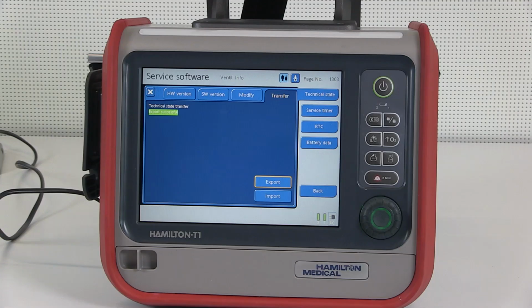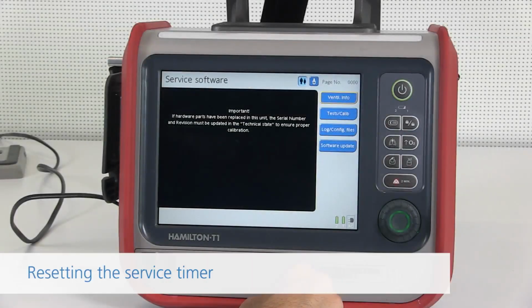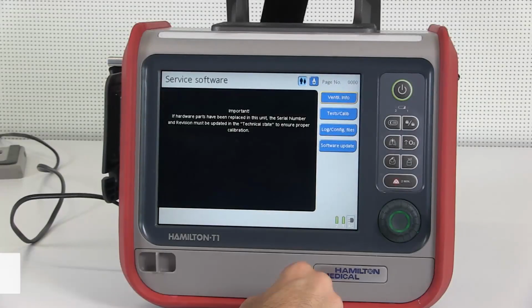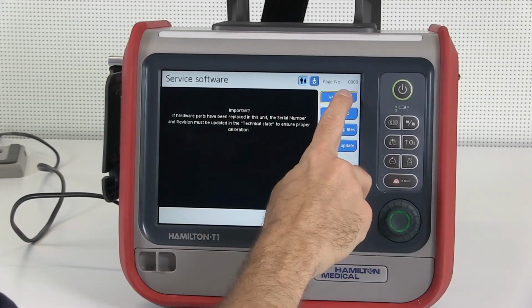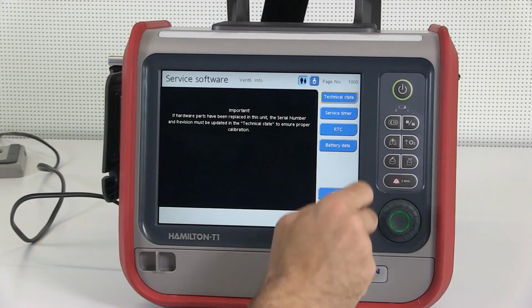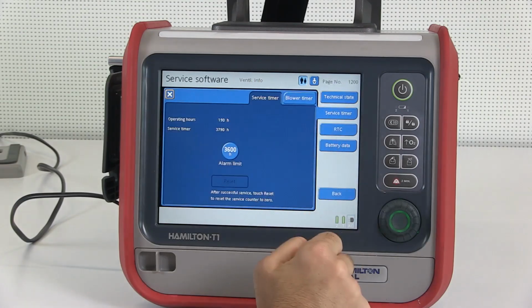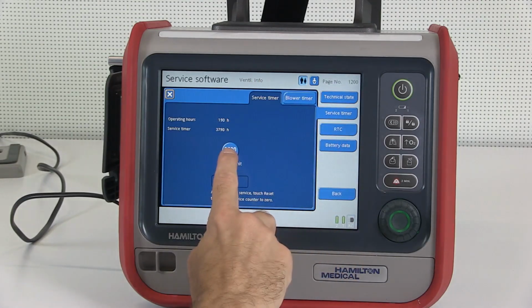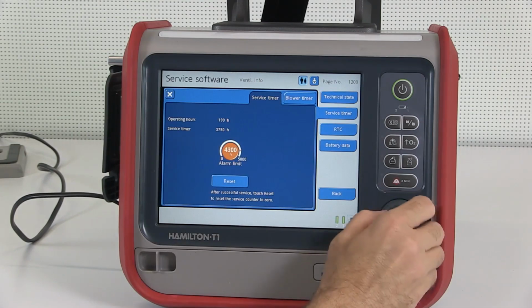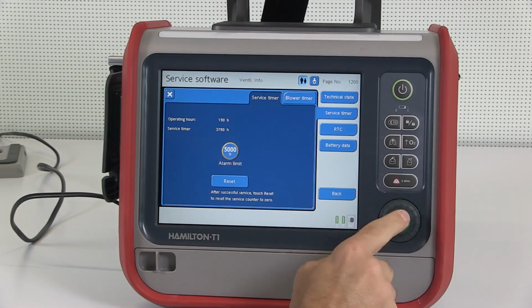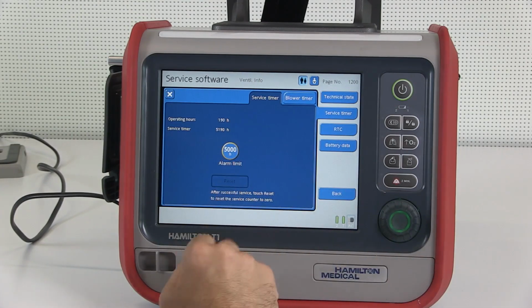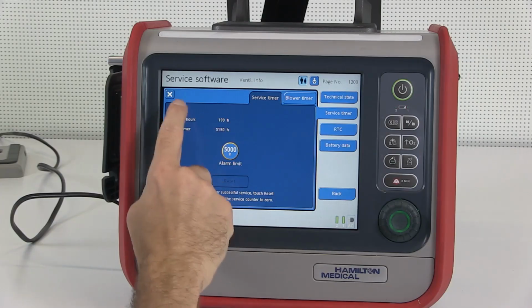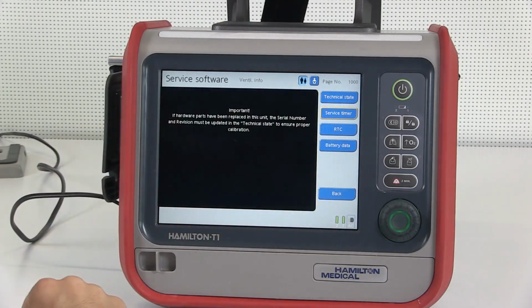After performing the preventive maintenance, you must also reset the service timer. Go to Technical State, then Service Timer. Change the service timer to 5,000 hours or the number of hours defined by the hospital to elapse before performing the next service. Then touch the Reset button. The ventilator will trigger a service required alarm after 5,000 operating hours.